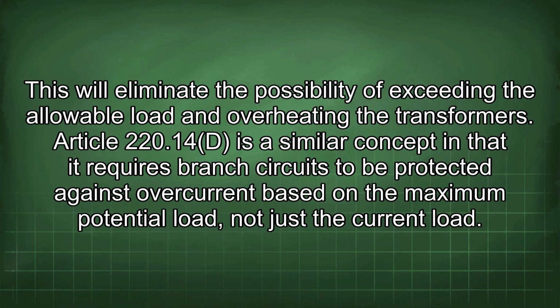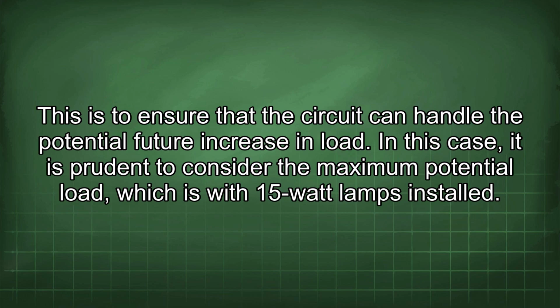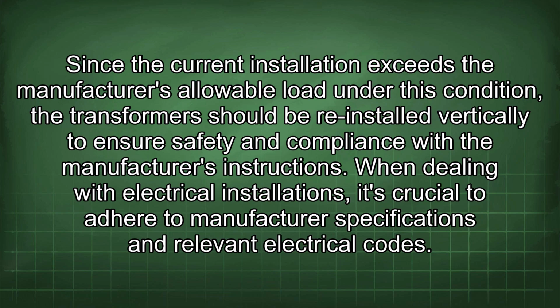Article 220.14(D) is a similar concept in that it requires branch circuits to be protected against overcurrent based on the maximum potential load, not just the current load. This is to ensure that the circuit can handle the potential future increase in load. In this case, it is prudent to consider the maximum potential load, which is with 15-watt lamps installed. Since the current installation exceeds the manufacturer's allowable load under this condition, the transformer should be reinstalled vertically to ensure safety and compliance with the manufacturer's instructions.